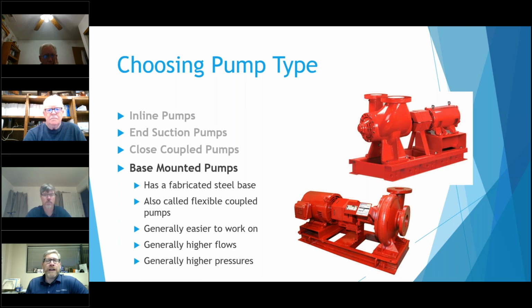I find these to be a lot easier to work on. Generally, you don't have to move the motor to repair the pump. Even these, the coupler drops out, and then there's enough space to pull the bearing assembly out of the volute, so you can go ahead and make repairs to it. So that's why I like to work on them. The components are also a lot lighter. Especially with these, you're just pulling out a bearing in this, or the seal kit, a lot lighter than pulling the whole motor out just to change a seal kit. Even this here, where those bearing assemblies do get quite large, you can usually still kind of muscle them out of there and make the repairs that you need to make.